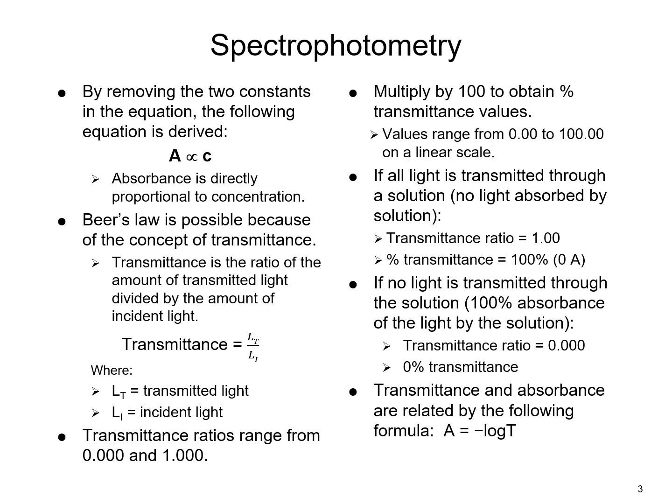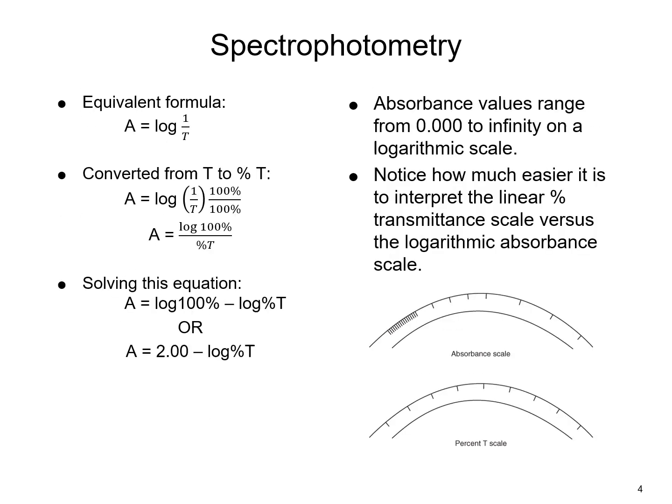Mathematically, transmittance and absorbance are related by the formula: A equals negative log of transmittance. We can manipulate that formula to get equivalent forms, and it can further be converted from transmittance to percent transmittance, ultimately giving the equation: absorbance equals 2.0 minus log of percent transmittance.